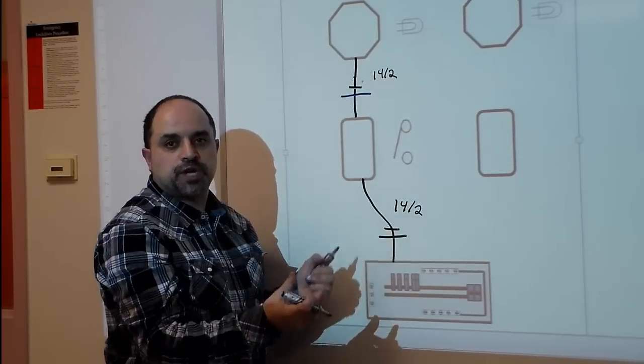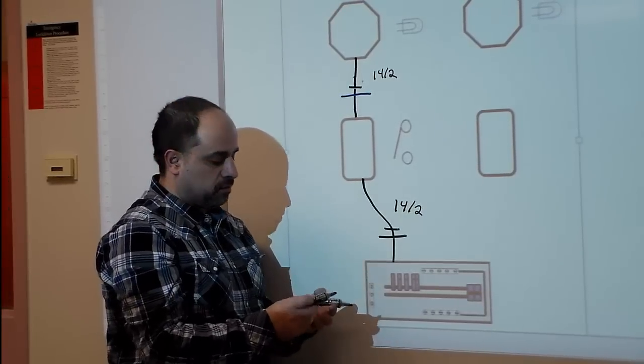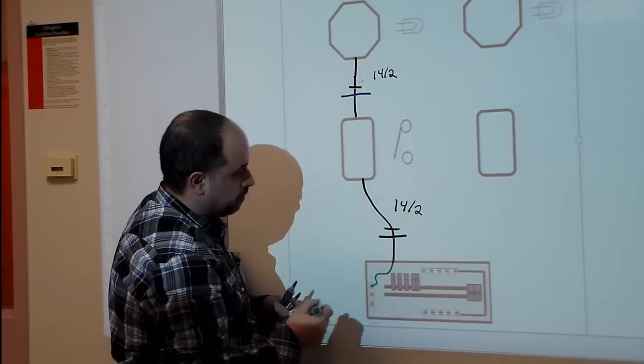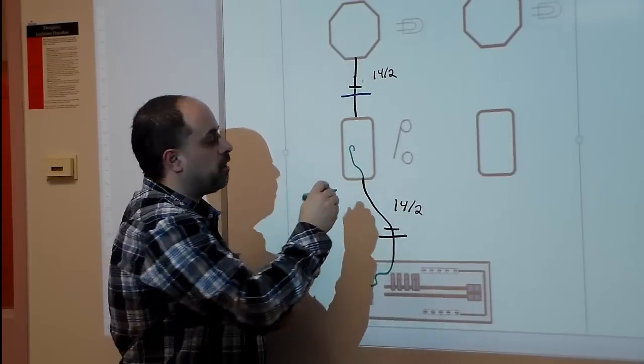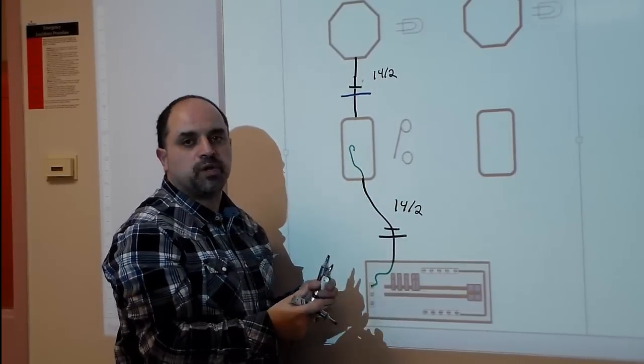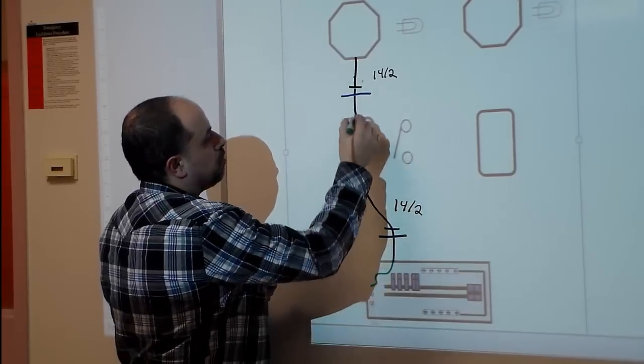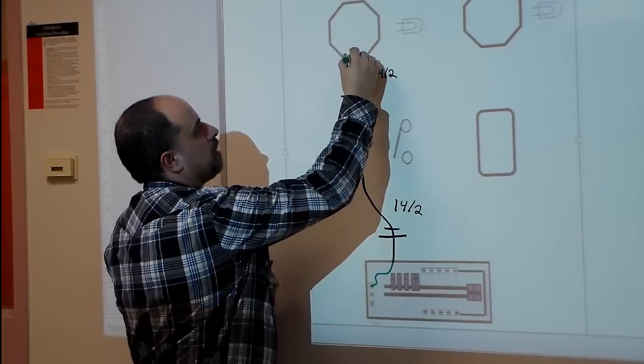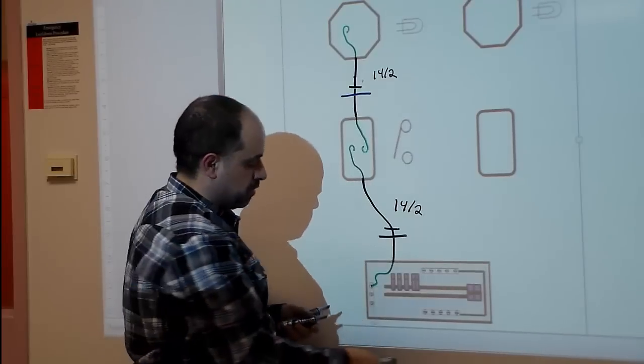Once you strip away the outer jacket of your 14-2, you're going to have three conductors in it: a black, a white, and a ground. In the panel, you're going to take your ground wire and hook it up to the ground lugs, and you'll do the same with the ground wire around the screw of the box — wrap it clockwise, because as you tighten the screw it will suck in the wire. You do the same for the other ground wires, and that takes care of our grounds.